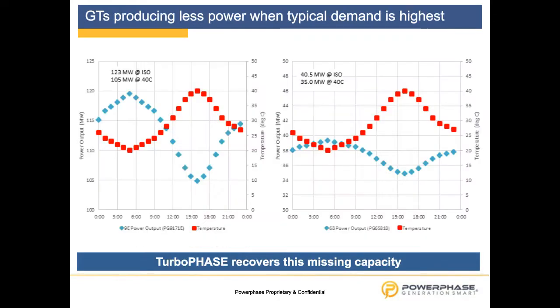In the next slide, I'm actually addressing what we do. You see here two typical temperature versus power patterns over a day. On the left side, you see a typical 9E power output, and on the right side, it's a 6B power output. What is shown here is that when the temperature is the highest, the output is the lowest, and that is simply caused by the density of the air at high temperatures, causing a reduced mass flow. And with a reduced mass flow, the gas turbine is unable to produce the required power. What we're doing is compensating for the missing mass flow, the missing capacity due to high ambient temperatures or high altitude.